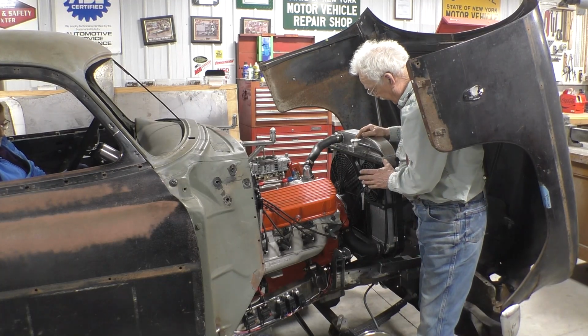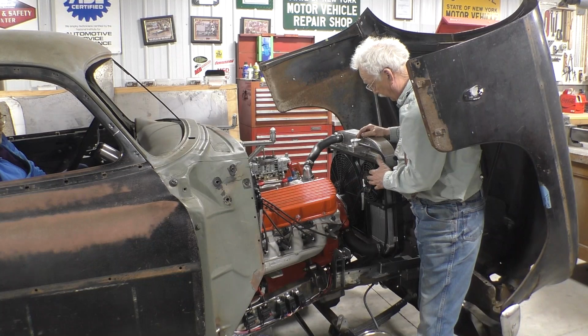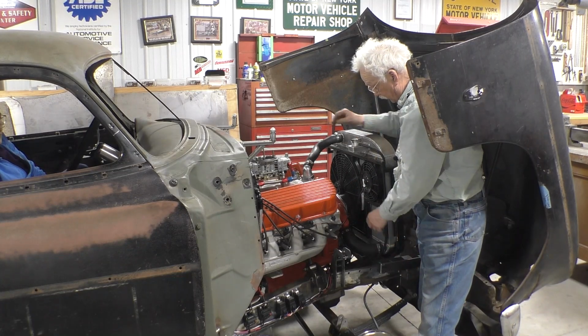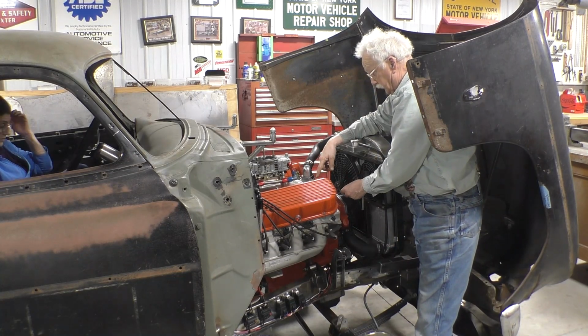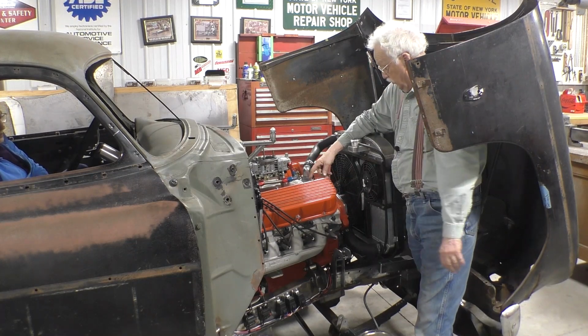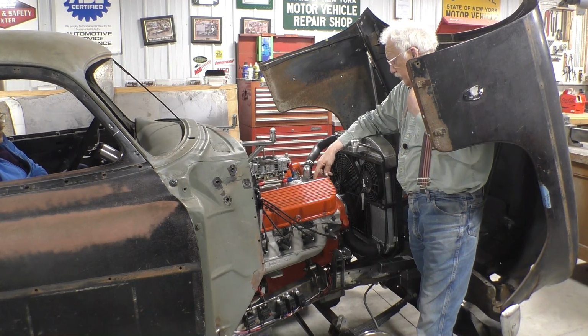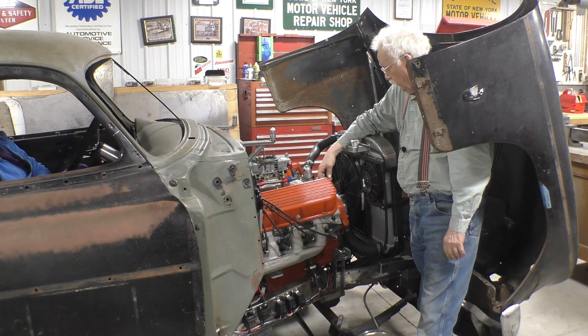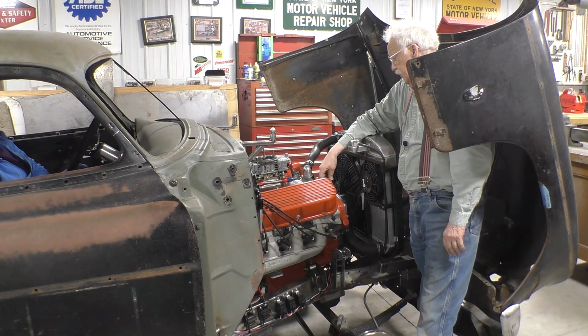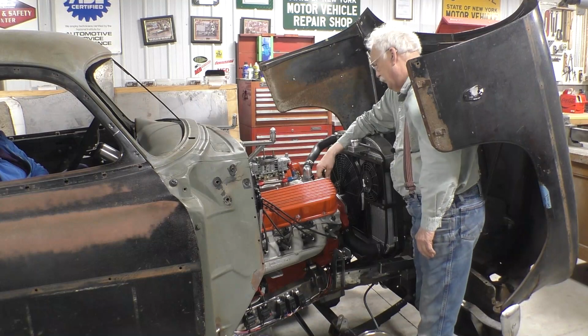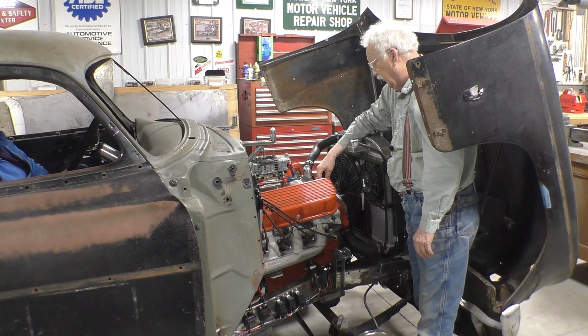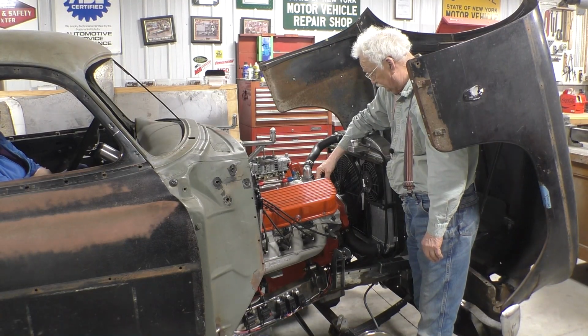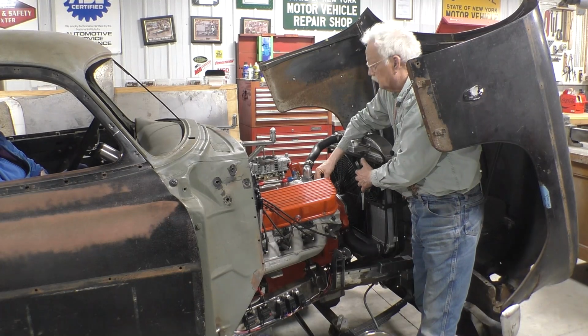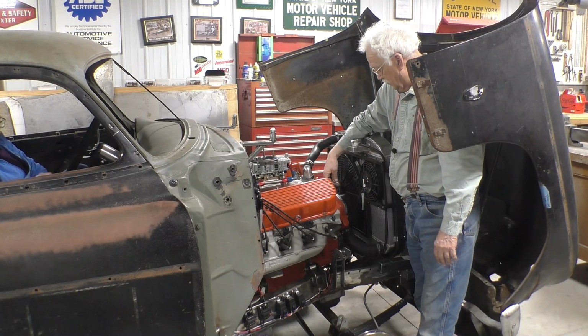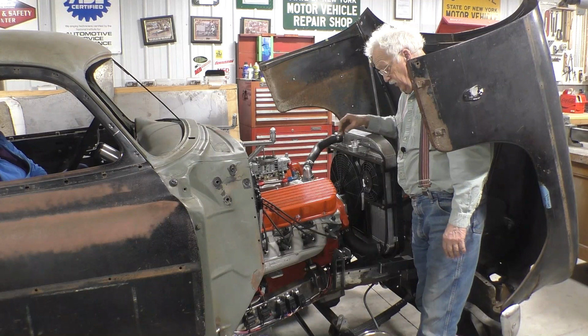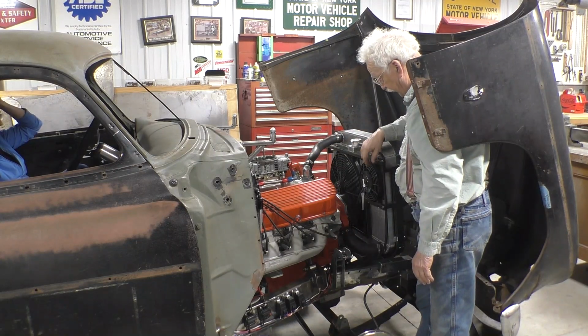The last thing we have to do is check the auxiliary fan. It runs on a temperature sensor and won't come on until we reach 185 degrees, so I'm going to fool it by grounding it to see whether it works, but it only works when the main fan is on. Can you turn the main fan on? Okay, turn it on. So the main fan runs and the auxiliary fan runs.